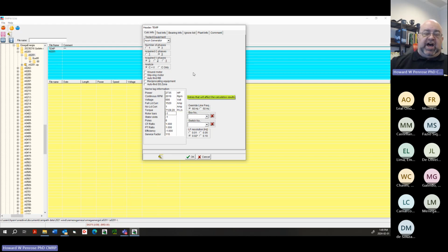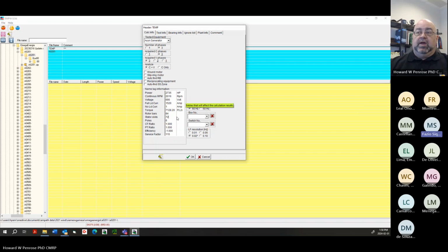Rotor bars are the rotor slots for a DFIG, or rotor bars for an induction machine. We use that because that is going to show us certain signatures in the high frequency spectrum. That will identify things like drive software. Can you repeat, please, the rotor bars? That's either rotor bars or rotor slots. So in a DFIG, which is a wound rotor generator, you'll have slots versus rotor bars. In an induction machine, you'll actually have copper bars that go through the length. It's the same thing. As a matter of fact, it sees it as the same thing. Whether it's coils or an actual copper bar in there, it's rotor bars.